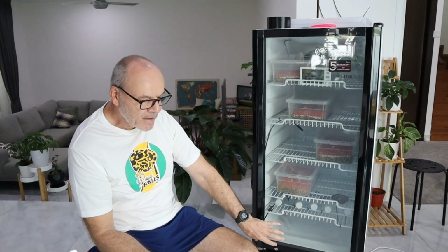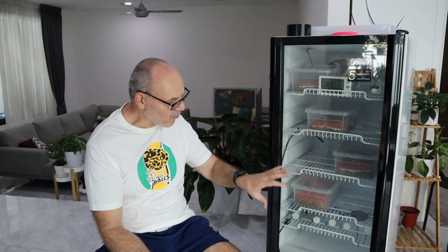Just remember with the fan that the fan itself is always a source of heat. For me in the tropics, that heat input is actually significant, and I will probably have to reset my thermostat in order to account for that heat, which means that you set your incubator up either with or without a fan, and the fan must be running all the time when you set your incubator up. You cannot have your fan running on the thermostat where it's switching on and off, because you disrupt the convection currents and you get a false reading inside your incubator.